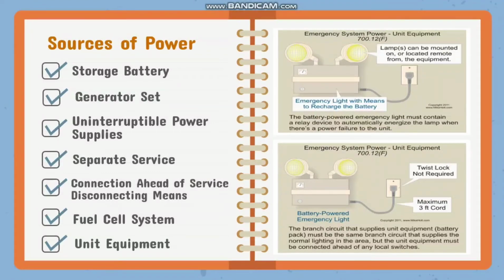The battery-powered emergency light must contain a relay device to automatically energize the lamp when there's a power failure to the unit. So requirement, twist lock not required. Maximum 3 feet cord. So the branch circuit that supplies unit equipment battery pack must be the same branch circuit that supplies the normal lighting in the area, but the unit equipment must be connected ahead of any local switches.